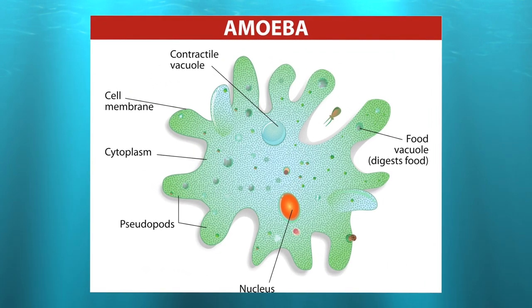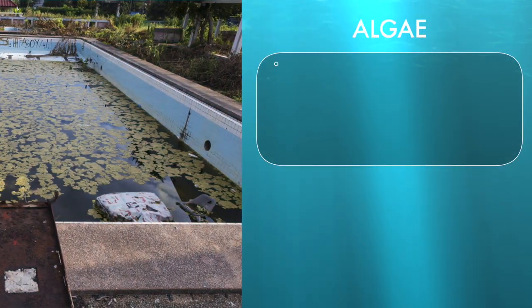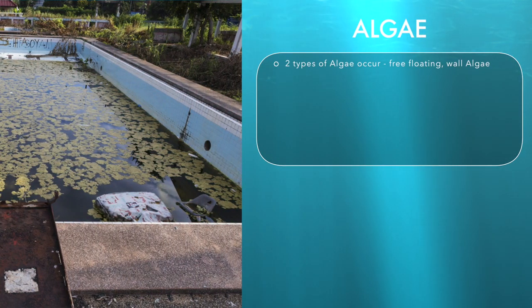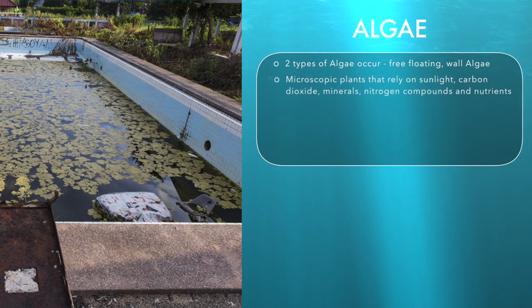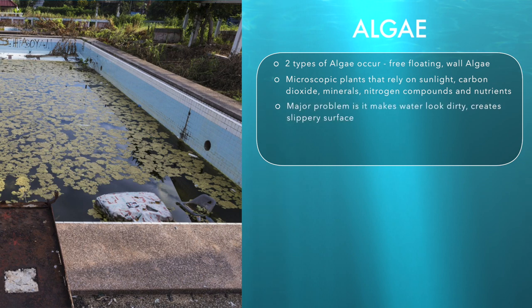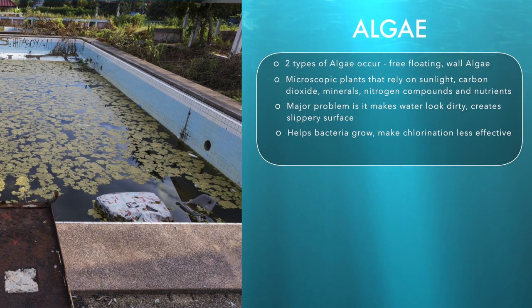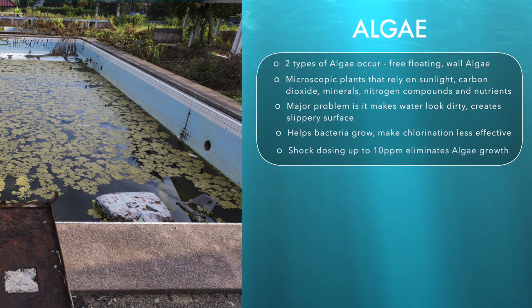There are two types of algae that occur in swimming pools: free-floating and wall algae. All algae are microscopic plants that rely on sunlight, carbon dioxide, minerals, nitrogen compounds and nutrients to grow. The major problem with algae is it makes the water look dirty and creates slippery surfaces which can cause accidents around the pool. Algae can also help bacteria grow and make chlorination a less effective disinfectant. Shock dosing up to 10 parts per million will eliminate algae growth.